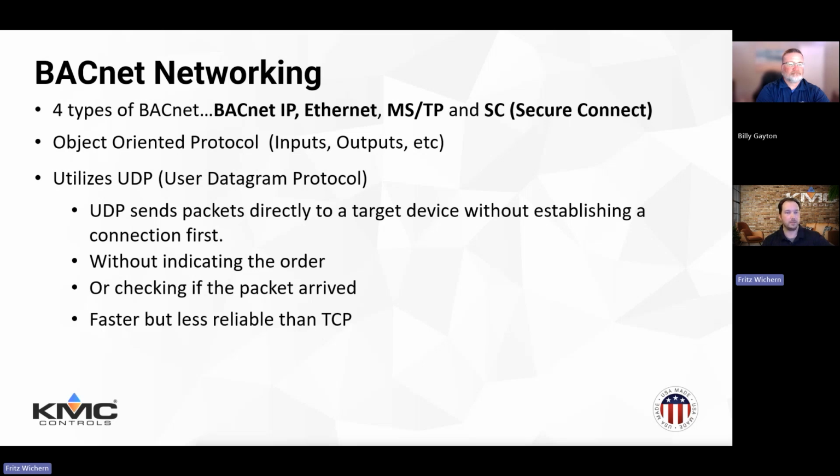BACnet Secure Connect is an addendum that was added to the BACnet protocol. It was released by the BACnet committee. It's a secure encrypted communication data link layer, specifically designed to meet requirements, policies and constraints for minimally managed to professionally managed IP structures.